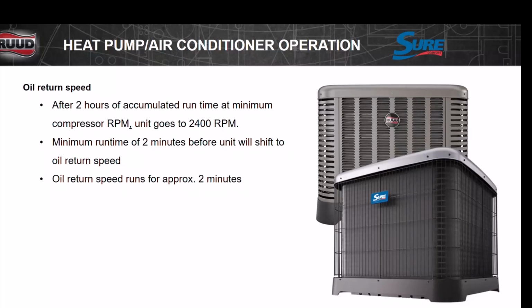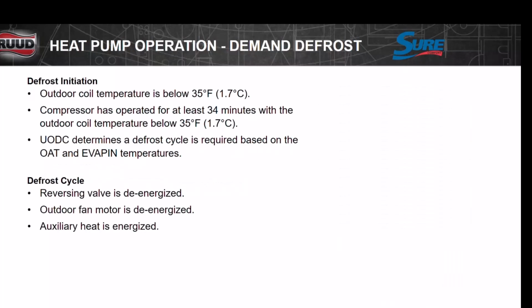Explain to them that occasionally they're going to hear it running in low cycles, and then they're going to hear it pick up. That's so we can get oil back. Running at low capacities all the time will push a lot of oil out into the system. So we have to ramp up the compressor to suck it back. Okay? Let them know that so you don't have these nuisance calls.